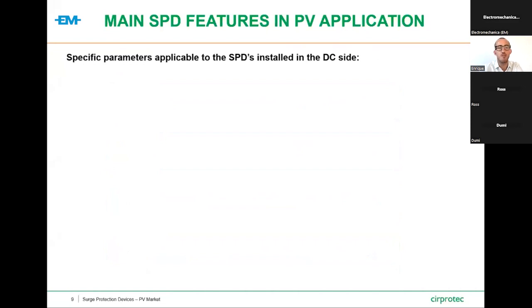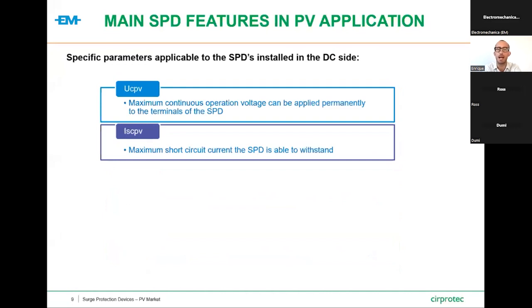Now, let's move on to the specific parameters applicable to the SPDs installed in the DC side of a PV installation. Here, we have two main parameters to have in mind. The first one is the Ucpv, which means the maximum continuous operation voltage that can be applied permanently to the terminals of the SPD. And then we have the Iscpv, which means the maximum short circuit current capacity the SPD is able to withstand.